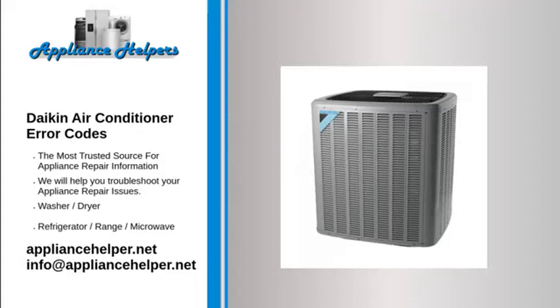Improper drain piping incline. Code AH. Problem: malfunction of dust collector of air cleaner. Defect of dust collecting element. Defect of high voltage power supply unit. Stained insulator part. Defect of indoor unit PCB.